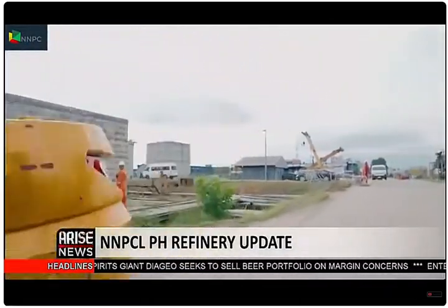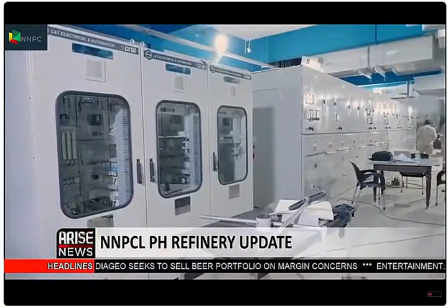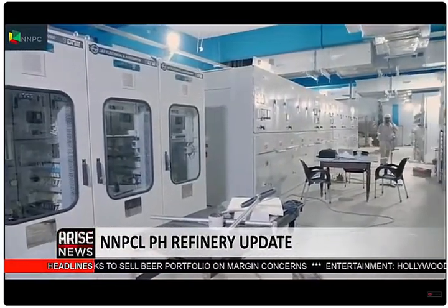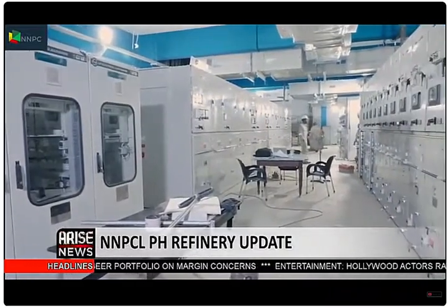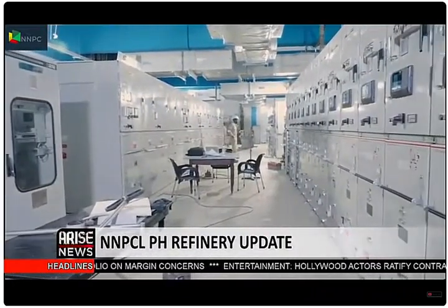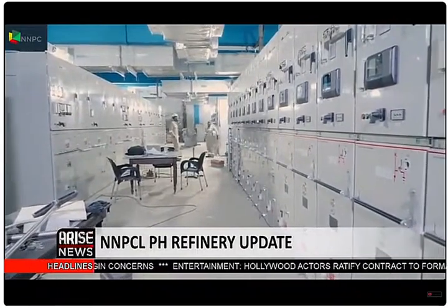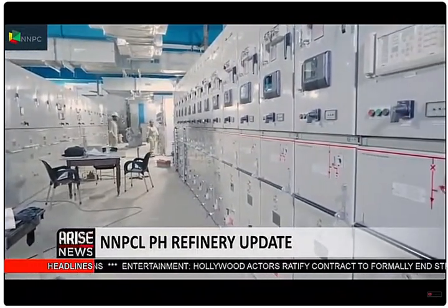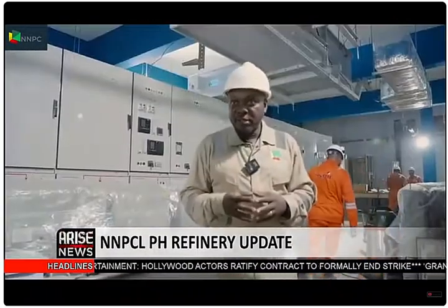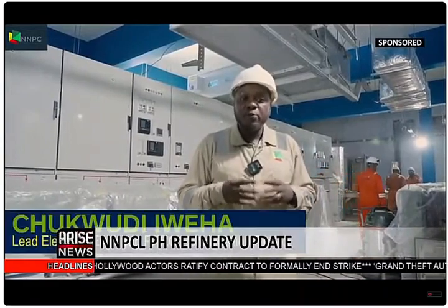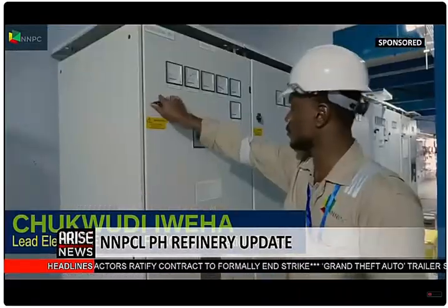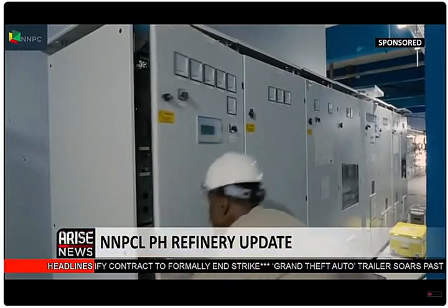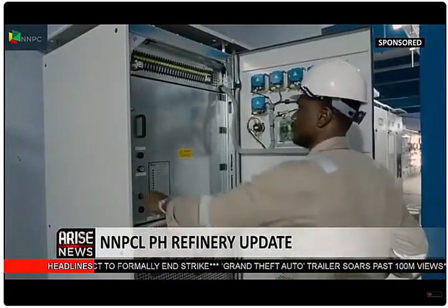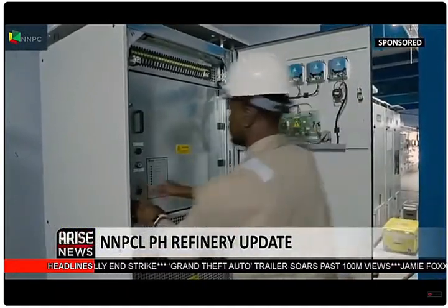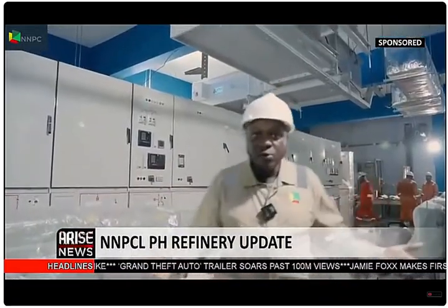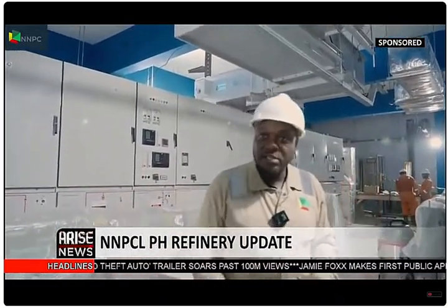Substation 1, which is the refinery's primary substation and powerhouse, will supply electricity to substations in the old and new refineries. It is designed to receive power from gas turbine generators. Right now we are at the testing phase, and we hope to finish the testing phase in a week, so that once we finish the testing phase and we're very sure we can commission here, I'm very sure by the next time you come in less than 2 weeks time, all the lights will be on and here would be up and energized. We call it energizing the substation.